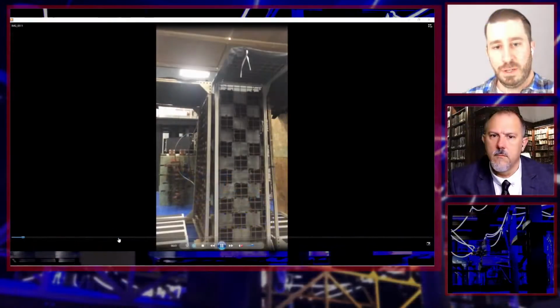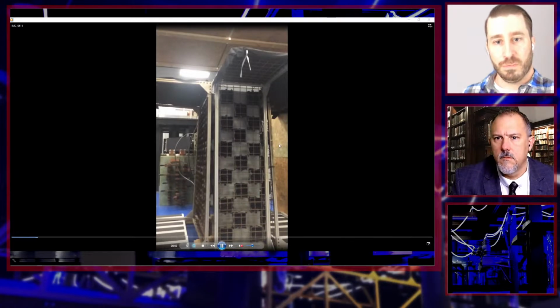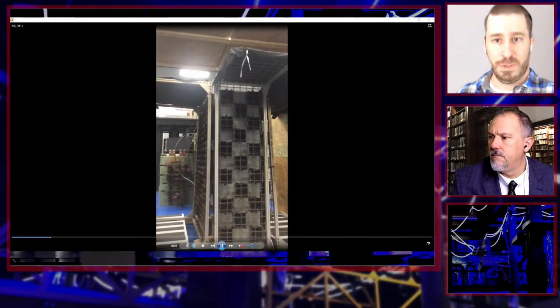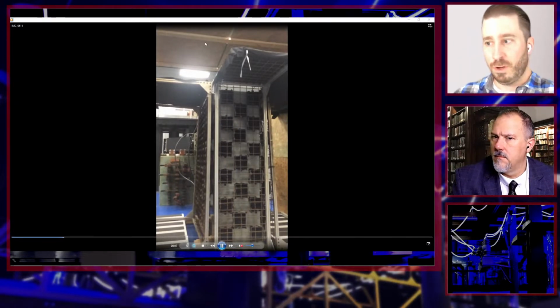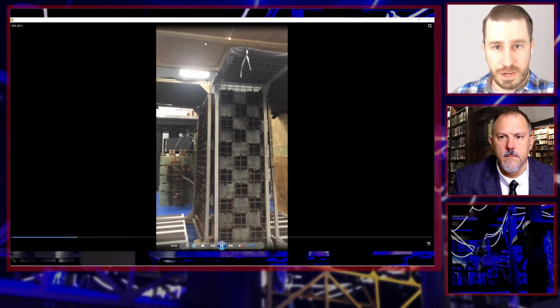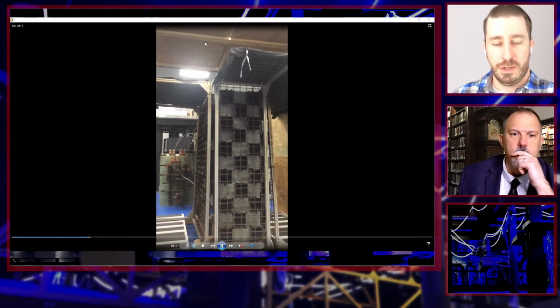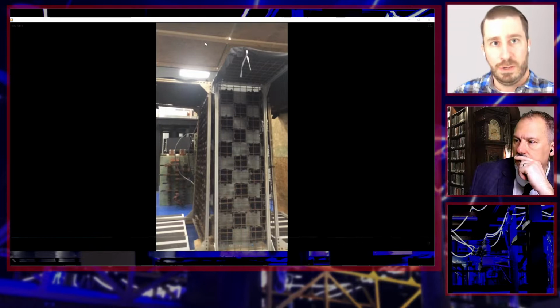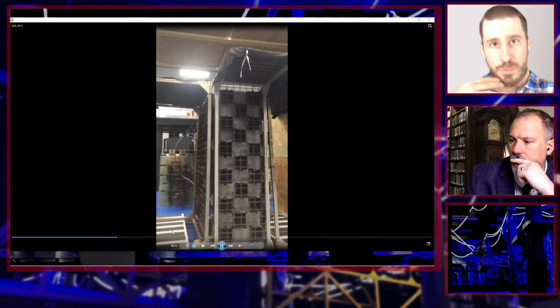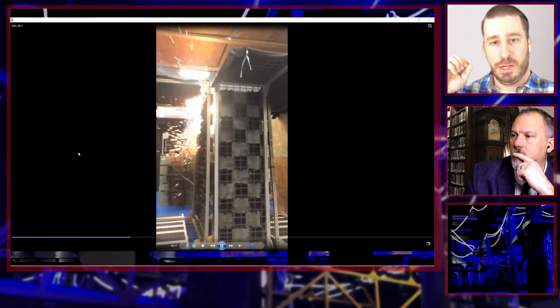In the setup, you can also see there's a little bit of a wooden building that we've constructed to mimic the effect of a room, recognizing that this equipment — you might have a wall that if that energy goes out on a particular side, especially with switchgear with an overhead plenum, you might have a deformation there.